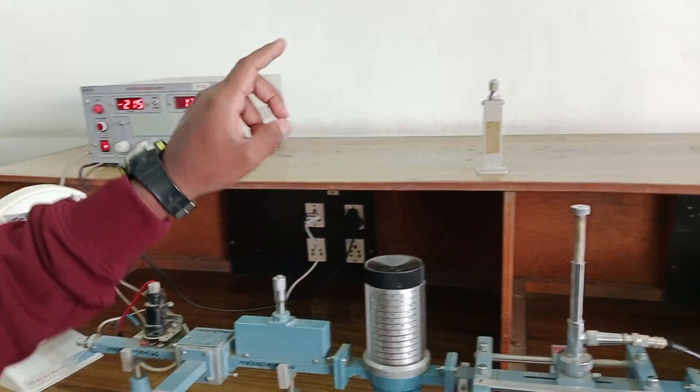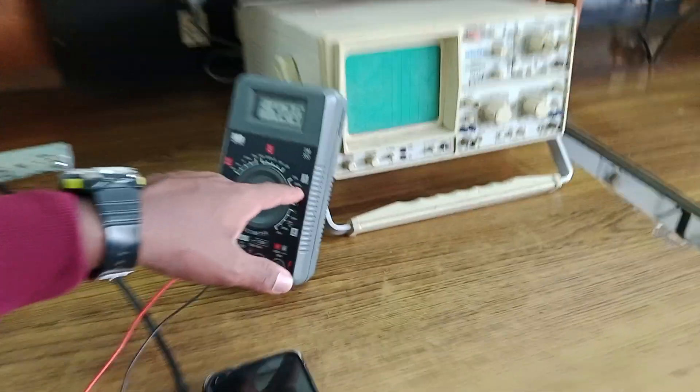And the second point is when you are connecting the meter, you have to keep it in the microamperes range, not in the milliamperes. You have to keep it in the microamperes range.